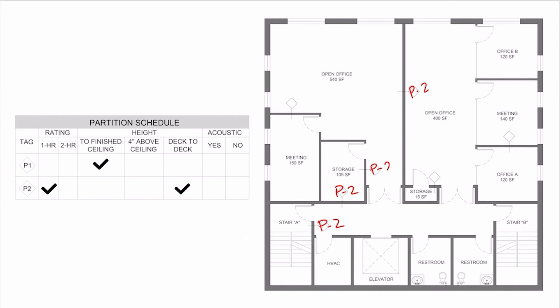There's one other partition tag that is going to be P2, and that is the storage unit that is greater than 100 square feet. We have another storage unit right nearby, but that one is only 15 square feet, so it's actually going to be P1 — it does not need to be a fire rated wall. Everything else: a wall dividing a meeting room and an office, and a wall dividing a meeting room and an open office, don't necessarily need to be fire rated, so those are P1.